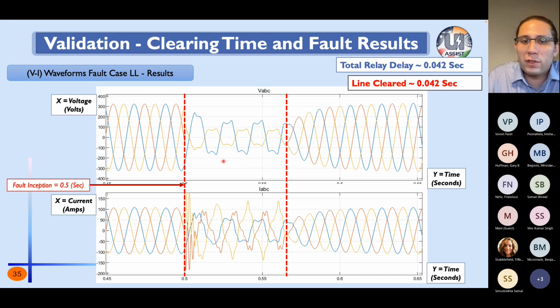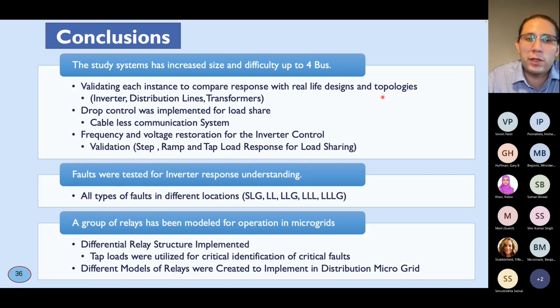We can see that when the fault is cleared, our grid is operational. In this case, we are opening the line, so we are still feeding the grid through the other lines. We are removing the fault, and once the fault is clear, we can return to normal operation. This is what we wanted to test. We know that clearing a fault takes 0.042 seconds. And I think with this I will come to the culmination of my presentation.